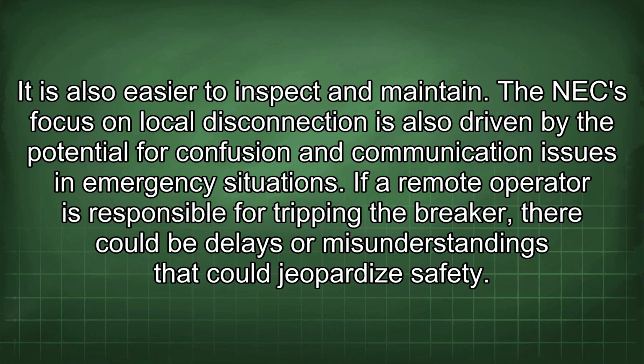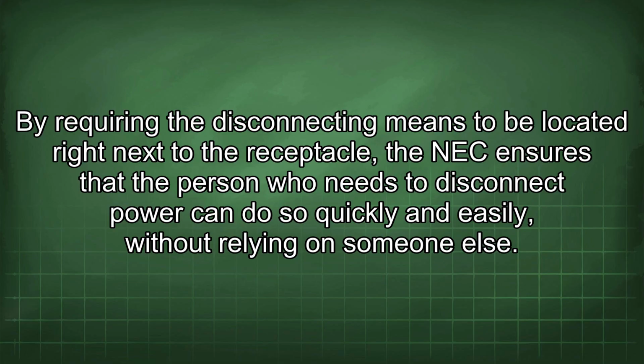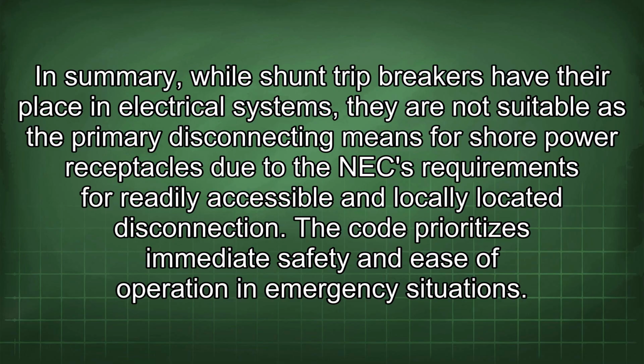The NEC focus on local disconnection is also driven by the potential for confusion and communication issues in emergency situations. If a remote operator is responsible for tripping the breaker, there could be delays or misunderstandings that could jeopardize safety. By requiring the disconnecting means to be located right next to the receptacle, the NEC ensures that the person who needs to disconnect power can do so quickly and easily without relying on someone else. In summary, while shunt trip breakers have their place in electrical systems, they are not suitable as the primary disconnecting means for shore power receptacles due to the NEC requirements for readily accessible and locally located disconnection. The code prioritizes immediate safety and ease of operation in emergency situations.